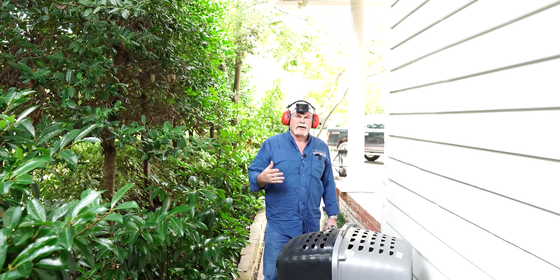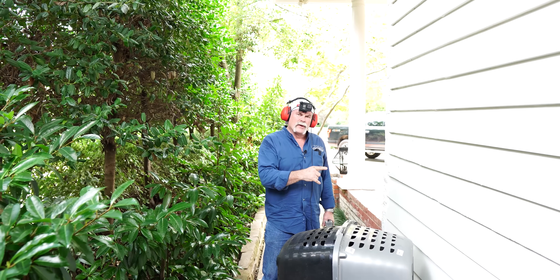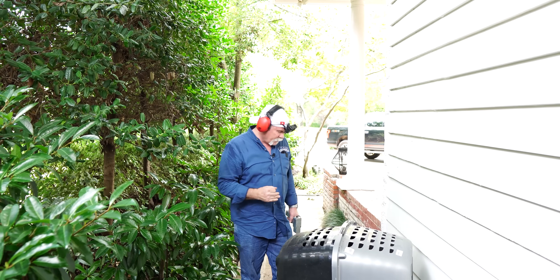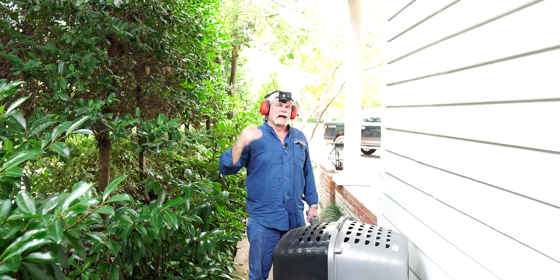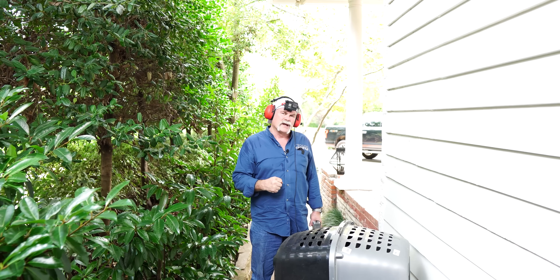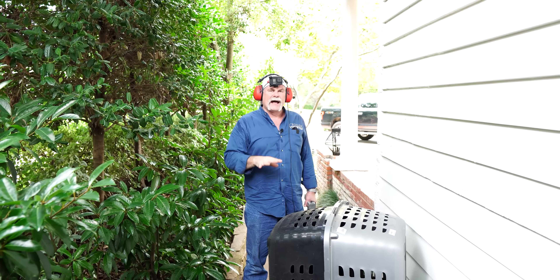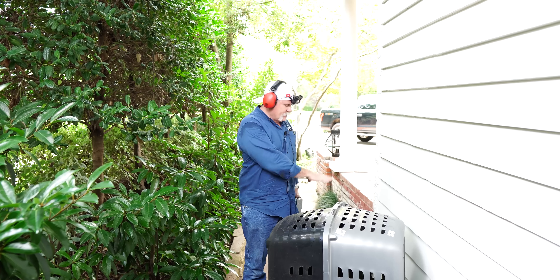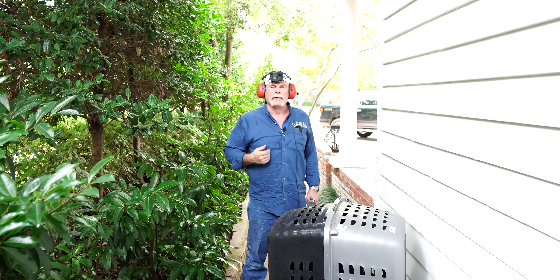I've listened to the frost proofs that I found outside and I don't hear anything. I turned on the one on the other side of the house and the one over here just to let some of the water out of the system. Because now what I can do is go back to the meter, open the meter and the double check, then turn the double check back on. If I don't see any water moving, I know that completely isolates the irrigation system only. These hose bibs are definitely tied into the potable water system — I know because I've been up under this house.